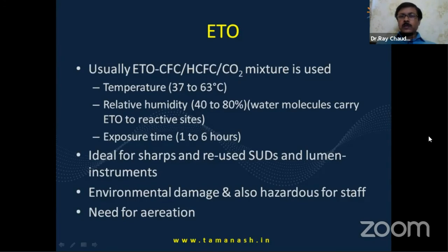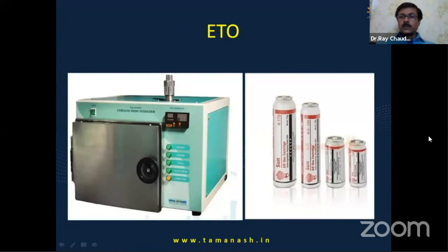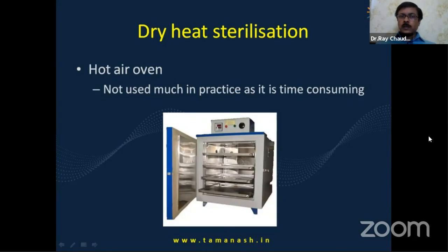The ETO is commonly a mixture of ETO with CFC or CO2. Nowadays, CO2 is preferred because CFC is an ozone depleting gas and is discouraged for environmental reasons. And this is ideal for sharps and reused single-use devices and lumen instruments. Environmental damage, and it is also hazardous to staff, so it has to be used with care. So ETO comes in these cartridges which have to be placed inside the chamber, and the machine has to be turned on. Nowadays, most ETOs are automatic, so they give a record of the temperature and pressure, temperature and humidity and time of the ETO.